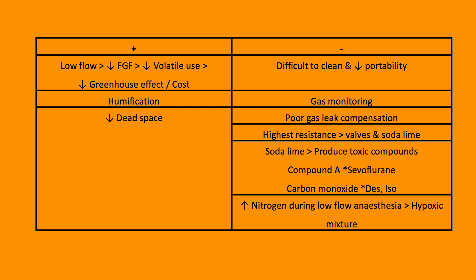However, the system is difficult to clean and difficult to move. It requires gas monitoring. There is poor compensation to leaks within the system, and it is a high resistance system due to the presence of valves and soda lime.